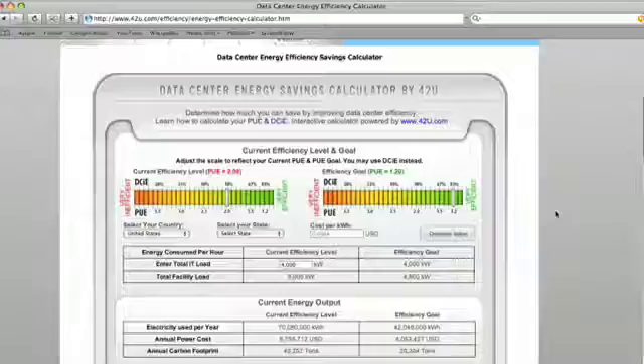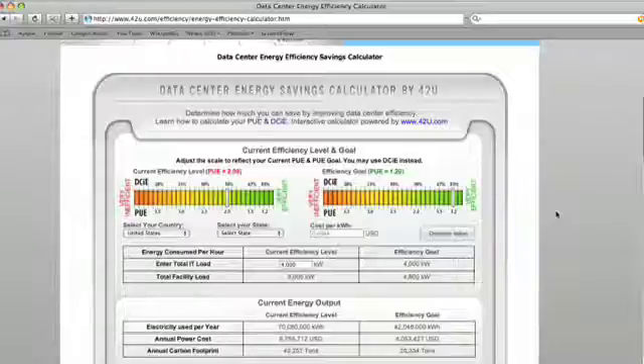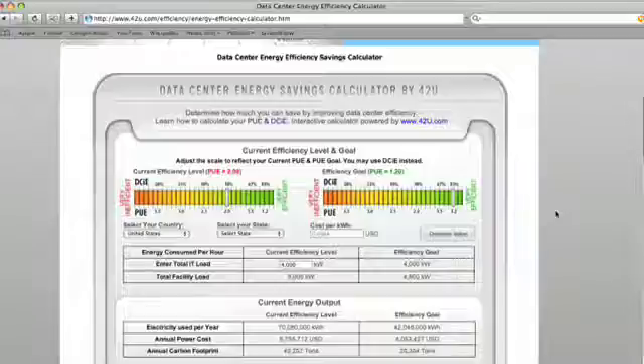The metrics involve the same two values: total facility load — the total amount of power required to run everything in your data center — and the IT load, which is the amount of power required by servers, storage, and switches to carry out the data center's purpose. Total facility load divided by total IT load results in PUE. Simply, these metrics are a ratio, a comparison between the energy required to do the data center's work and the energy required to support that work, such as air conditioning, power distribution, and lighting.